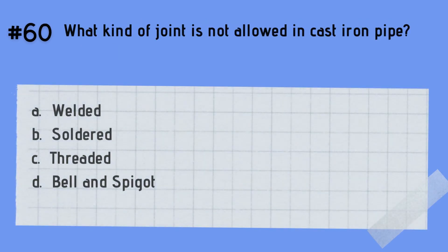Question 60: What kind of joint is not allowed in cast iron pipe? A. Welded. B. Soldered. C. Threaded. D. Bell and spigot. The answer is C — threaded. Threaded joints are not allowed in cast iron pipe. Instead, caulked joints are usually used for bell and spigot cast iron pipe, firmly packed with oakum or hemp. The finished joint shall not extend more than 3.2 mm below the rim of the hub.